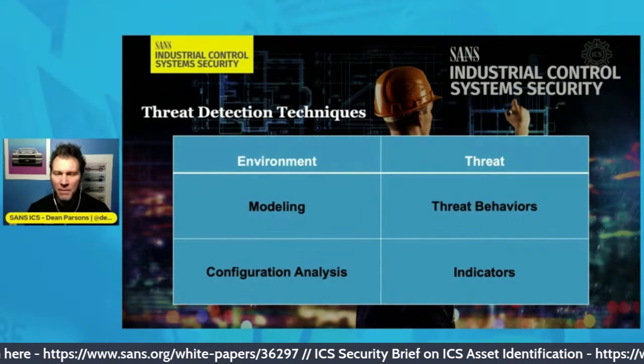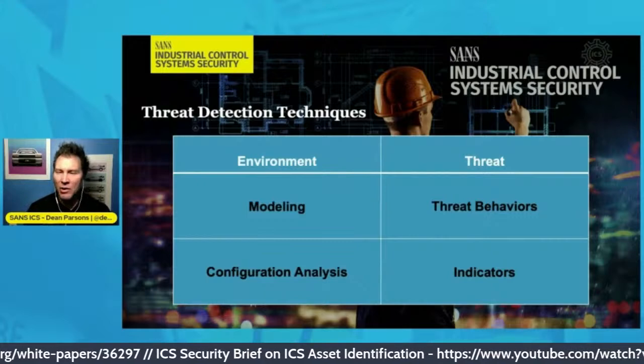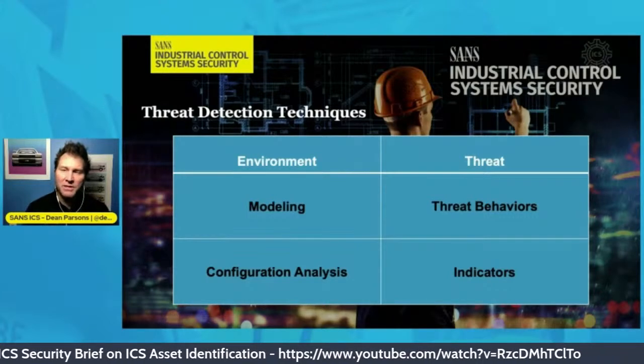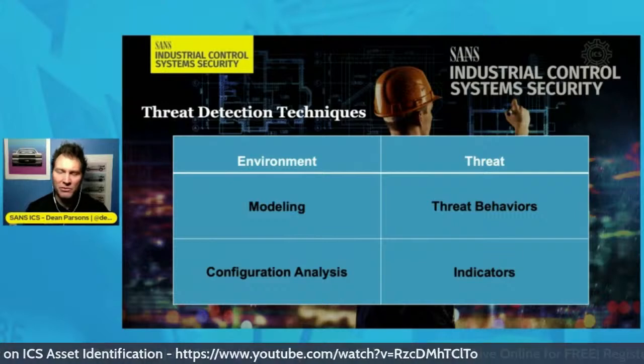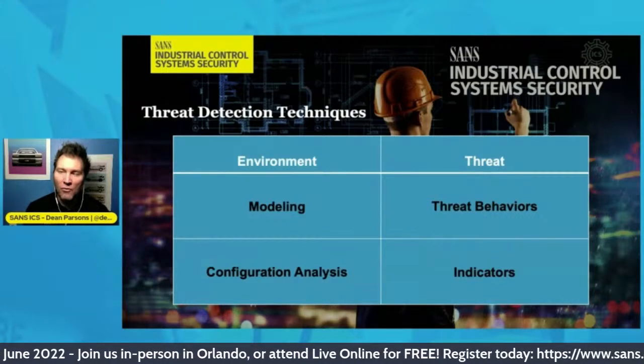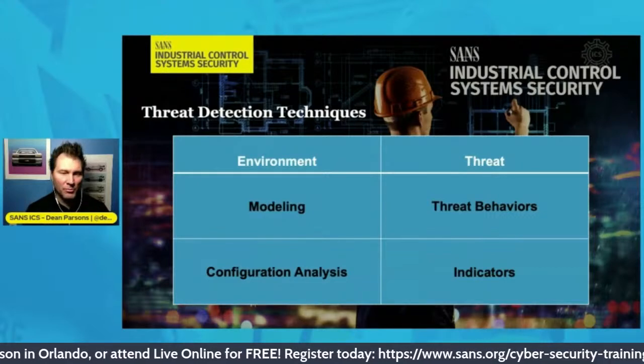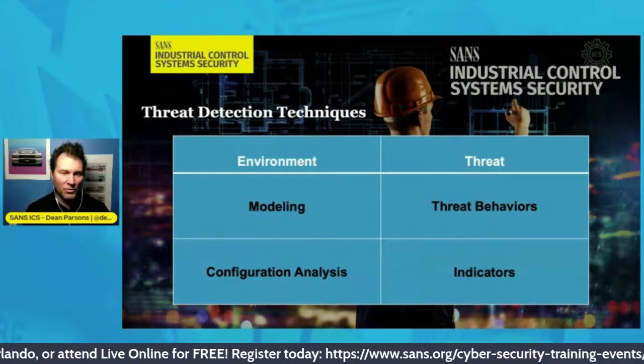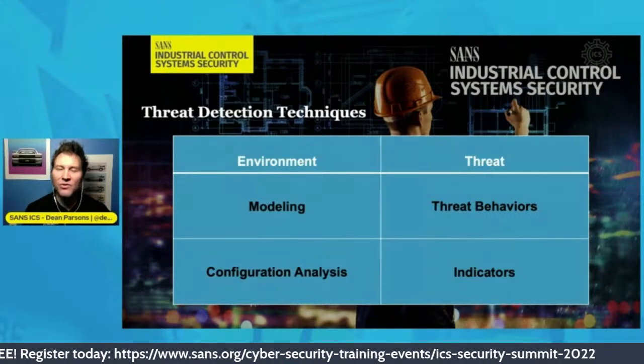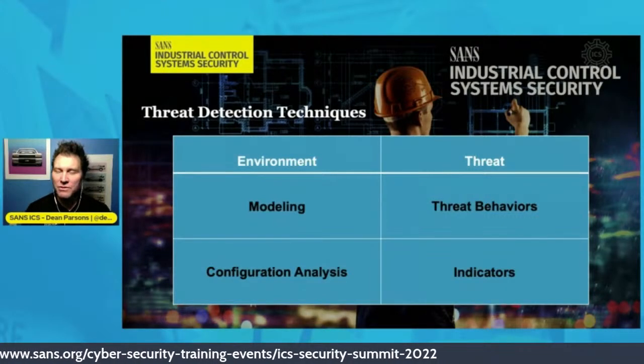To reduce false positives, moving away from configuration analysis, we can deploy modeling in the environment, which means we can allow some changes over a period of time. For example, we can allow project files to be uploaded and changed in the PLC over X number of times and N number of days, reducing the false positives. You may have to tune it, but again, detecting changes at the lower level of the control system.